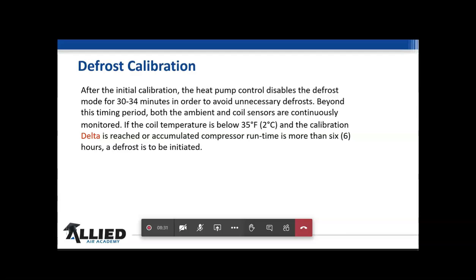Beyond this timing period, both the ambient and coil sensors are continuously monitored. That's what I told you about the forward learning, backwards learning, forward thinking, backward thinking. So if the coil temperature is below 35 degrees in calibration delta, and you'll see I got delta written in here in red because this is going to be a topic for us to talk about, is reached, or accumulated compressor runtime of more than 6 hours. So if it's run 6 hours and it hasn't gone into a defrost, then it will. No matter what the sensors are saying, it's going to go into a defrost, and just check it. So delta is what I really want to start talking about and making sure we understand exactly what that is.